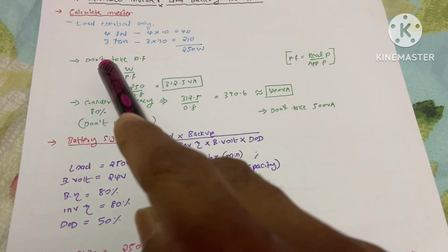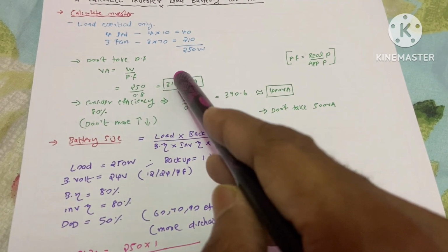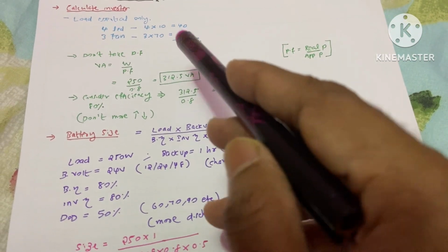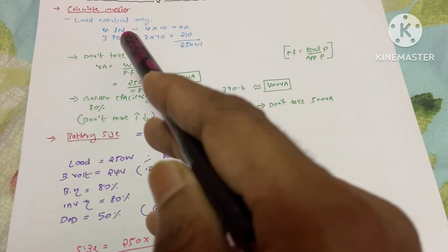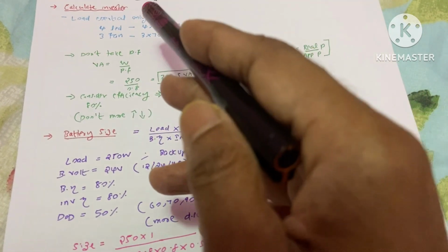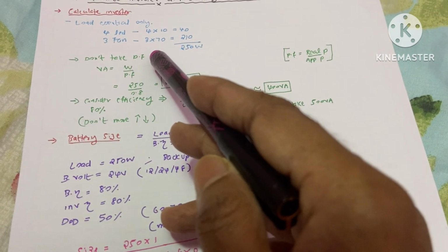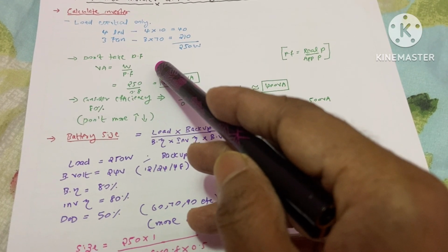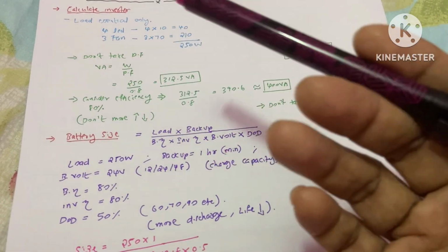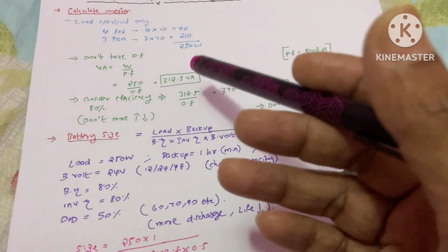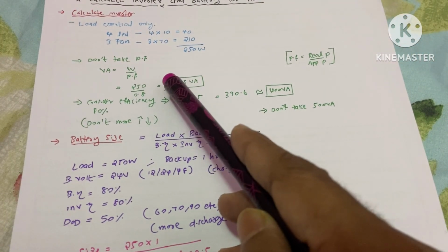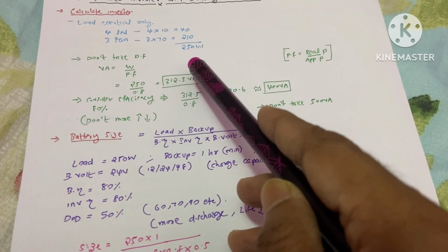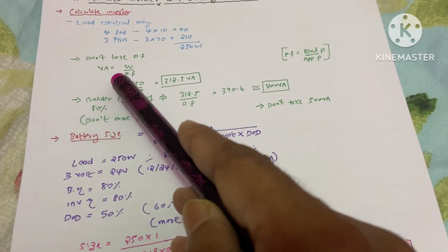And here there is no need to take a diversity factor because whenever there is a power loss in our home, we would use all the LEDs or fans which are connected to the inverter. We would normally take the diversity factor when we size the SNDB, MDB, or transformer, but here there is no need of that. So we need to convert the watts into VA because the inverter sizing would be in VA.